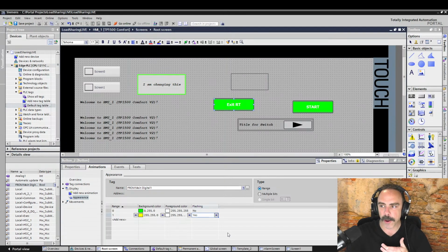Earlier I talked about how you'd never want to set your appearance to be flashing just because it's kind of obnoxious. Well, if you use animations, it's totally fine to do flashing, because you can set it up so that if there's no fault on my drive, my little fault number isn't going to be flashing red. So that's what we do here.